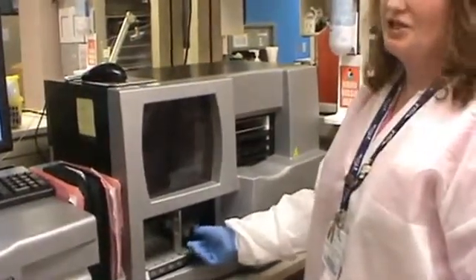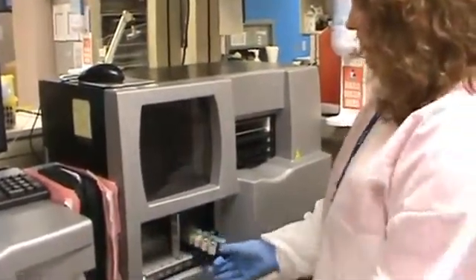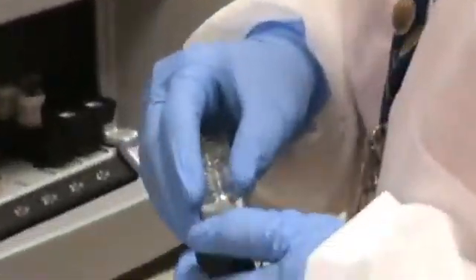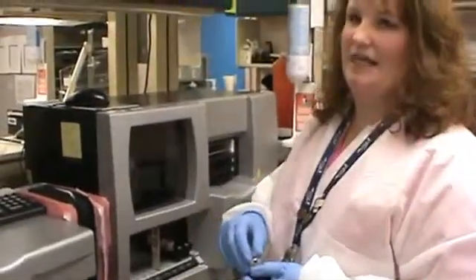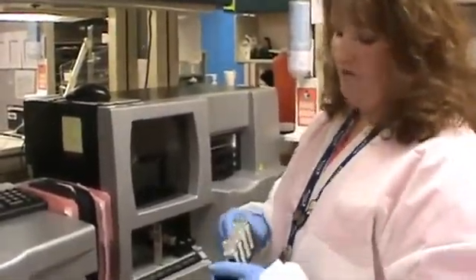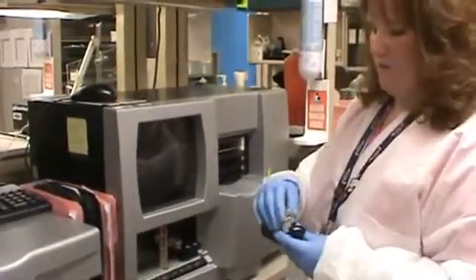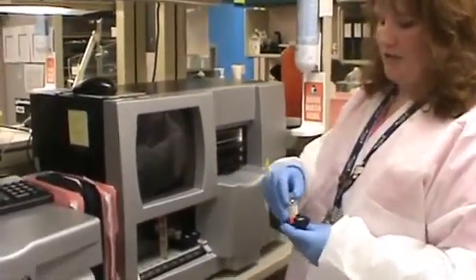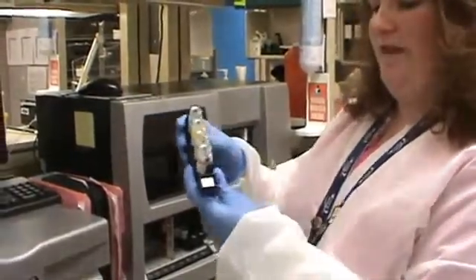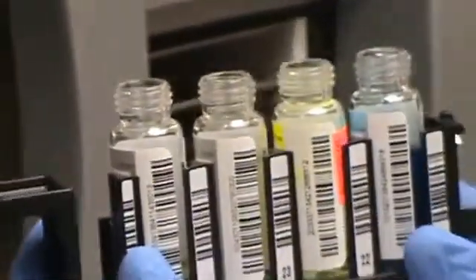Your barcodes for your reagents will include your lot number, your expiration, and also the Galileo Echo is capable of holding onto information as far as how many times the bottle has been on and off the machine and the total amount of time the bottle has been on and off the machine. The racks for the reagents have a symbol on them that resembles a reagent bottle. There are 4 slots on the reagent rack for a total of 16 reagent bottles that can be on the analyzer at any given time.